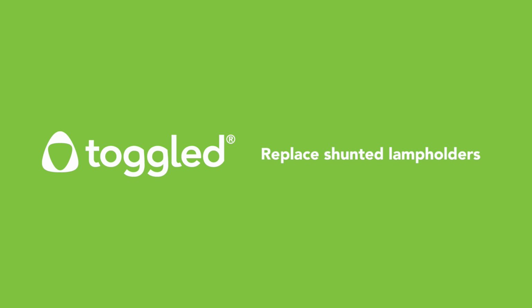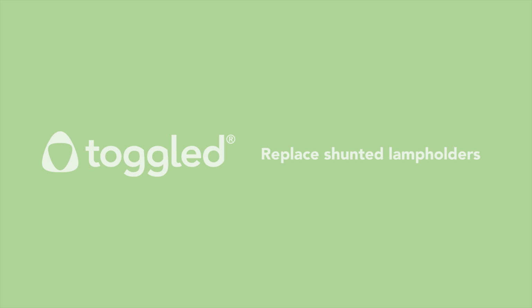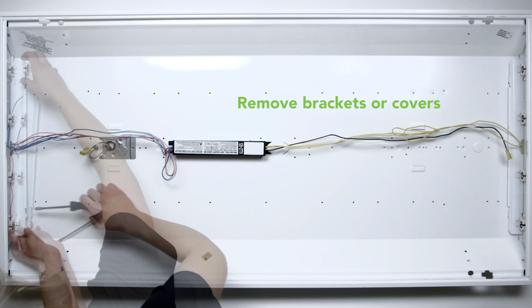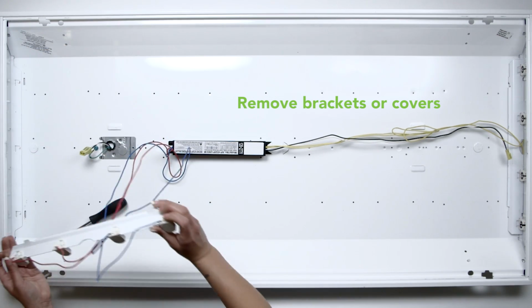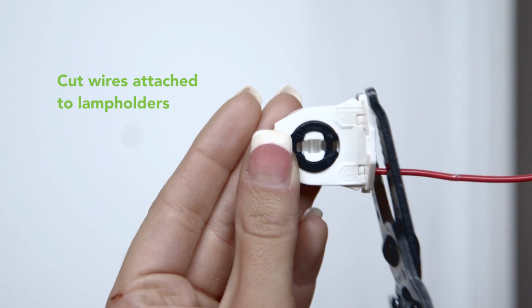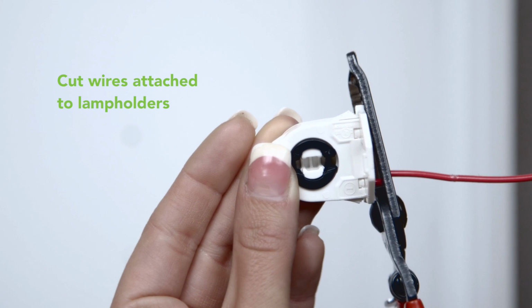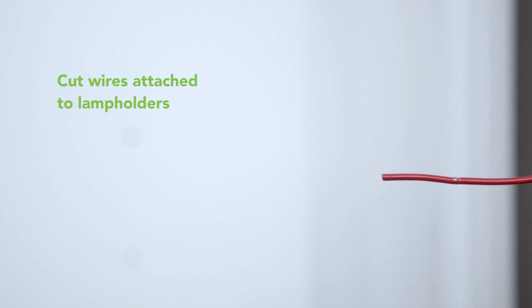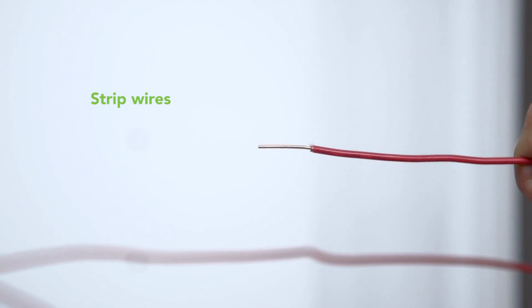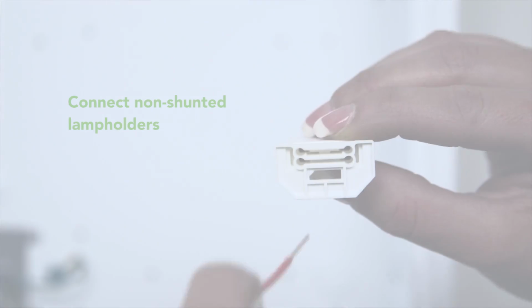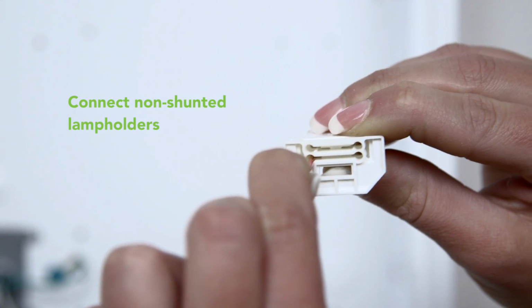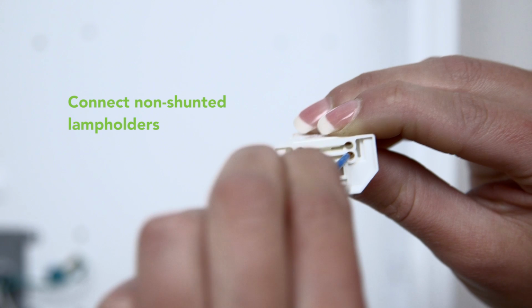To replace shunted lamp holders, follow these easy steps. Remove any brackets or covers holding the shunted lamp holders in place. Cut any wires attached to the lamp holders, being careful to cut the wires as closely as possible to the lamp holders so you can reuse the remaining wire. Strip wires according to the strip gauge on the new lamp holders. If a gauge is not available, strip wires to 3/8 of an inch or 9 millimeters. Insert one wire on each side of the lamp holders so that they can be connected to line and neutral later.